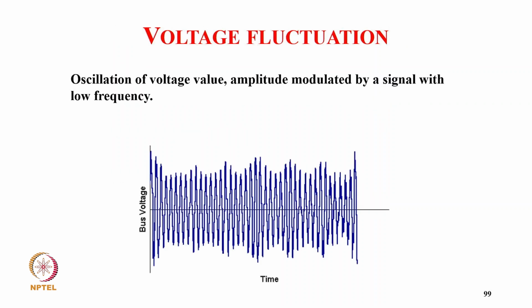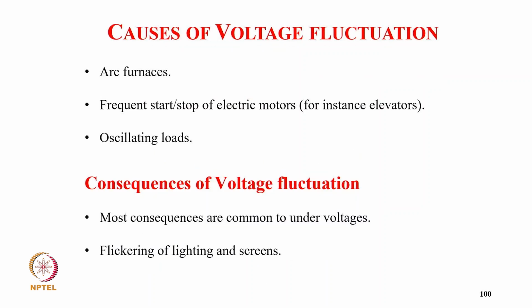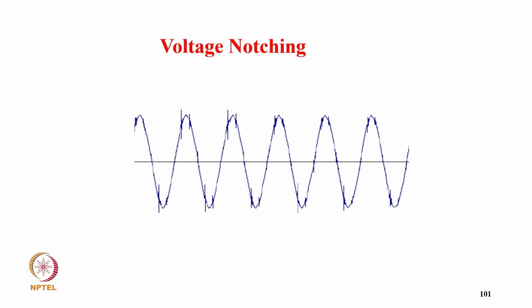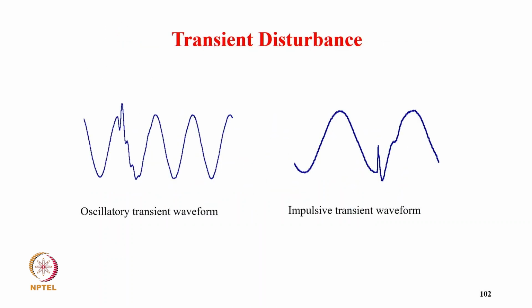Voltage fluctuations: oscillation of voltage value, amplitude modulated by a signal with low frequency. Causes of voltage fluctuations: arc furnaces, frequent start-stop of electric motors, for instance elevators, oscillating loads. Consequences of voltage fluctuation: most consequences are common to undervoltage, such as flickering of lighting and screens, and voltage notching, as you can see here.